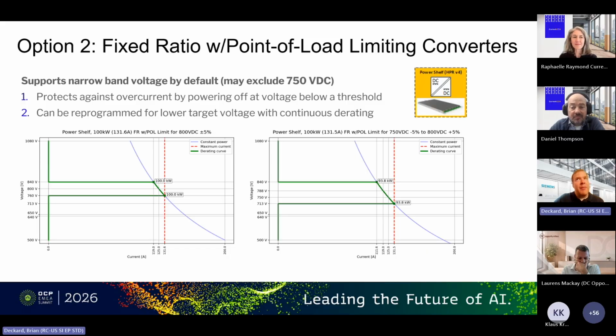So there's more or less a couple of possibilities. One, you could take a de-rate hit across the entire curve to open up the voltage window, or another possibility would be to design in the first place for a little bit higher increase in the maximum current, so that in a forward-planning way you could support full power at, say, plus 750 with one converter and minus 750 with another.